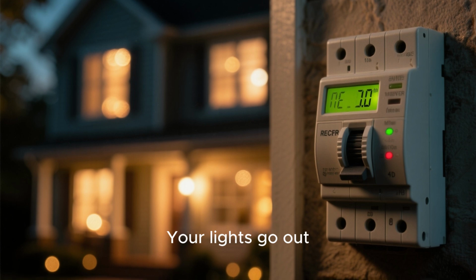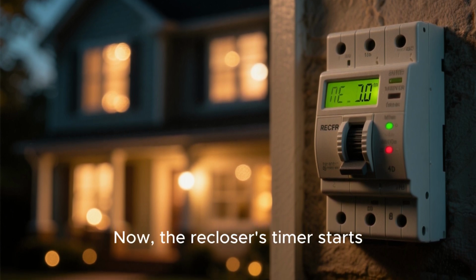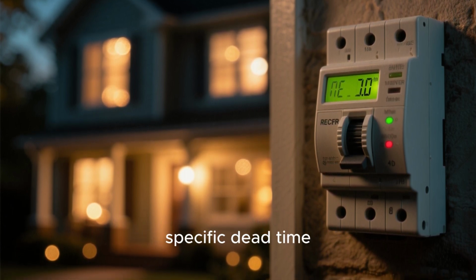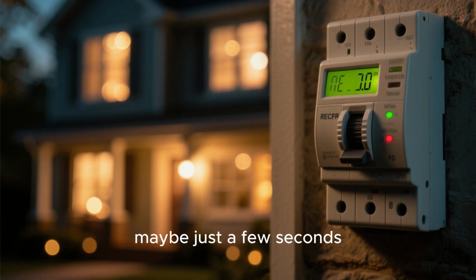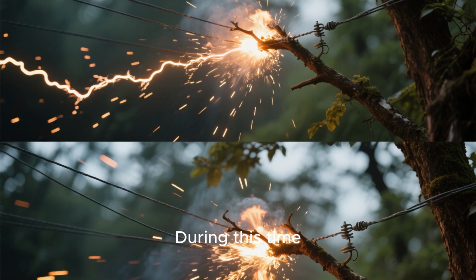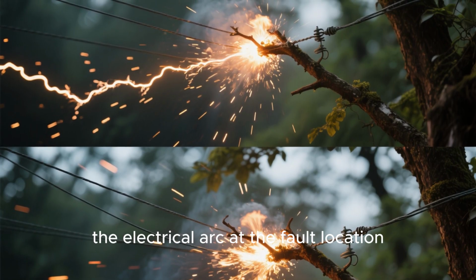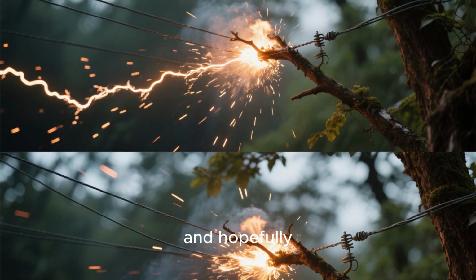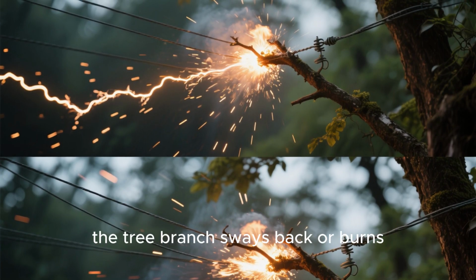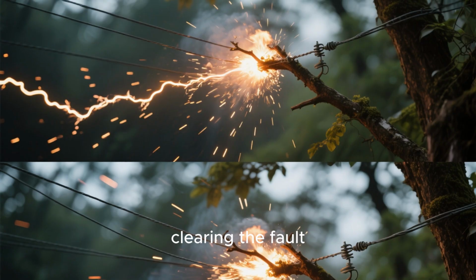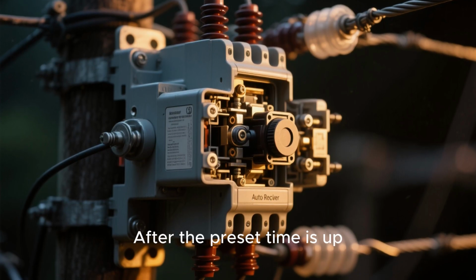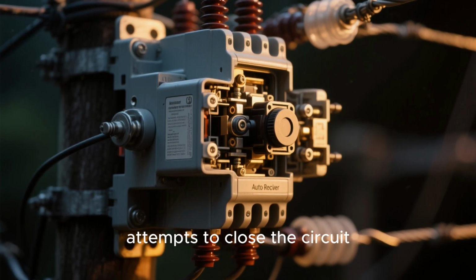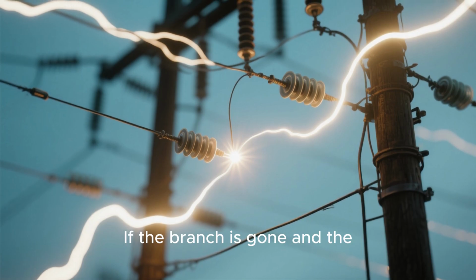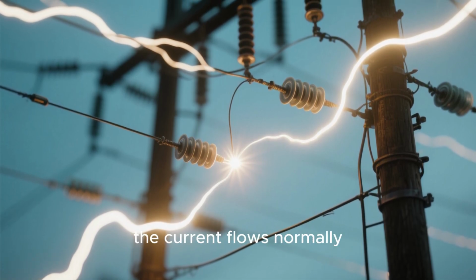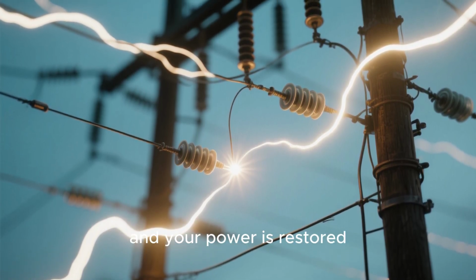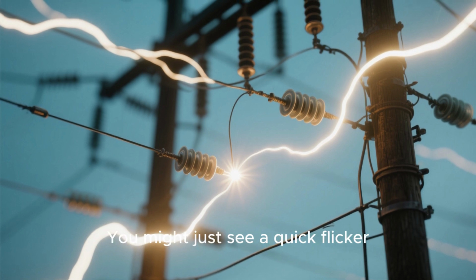Your lights go out. Now, the recloser's timer starts. It's programmed to wait for a specific dead time, maybe just a few seconds. During this time, the electrical arc at the fault location extinguishes, and hopefully, the tree branch sways back or burns away from the line, clearing the fault. After the preset time is up, the recloser automatically attempts to close the circuit. If the branch is gone and the fault is cleared, the current flows normally, and your power is restored. You might just see a quick flicker.